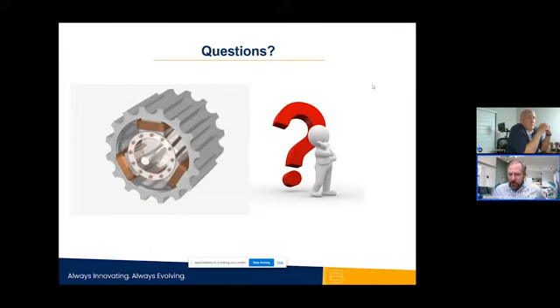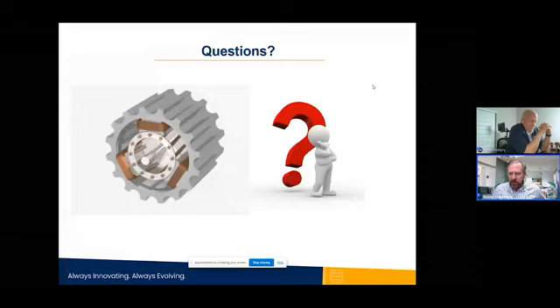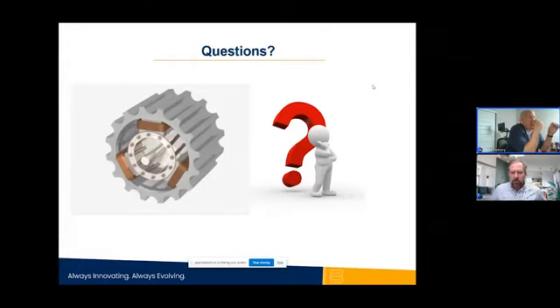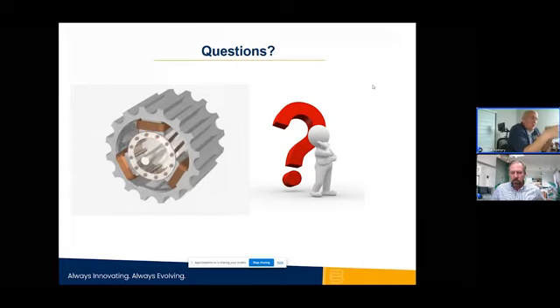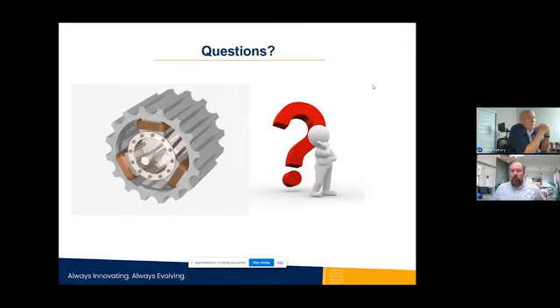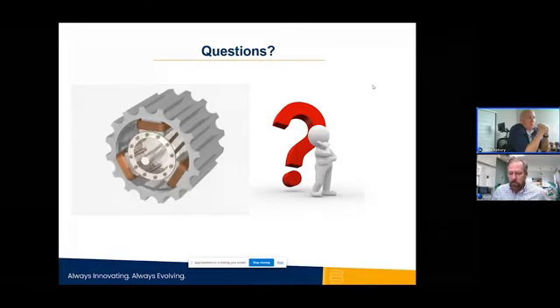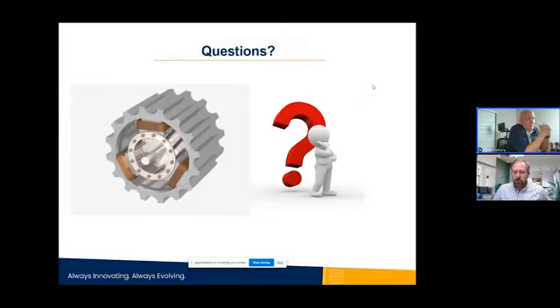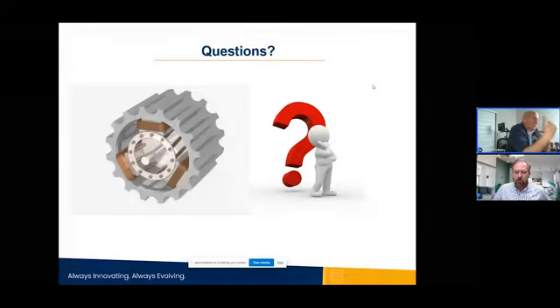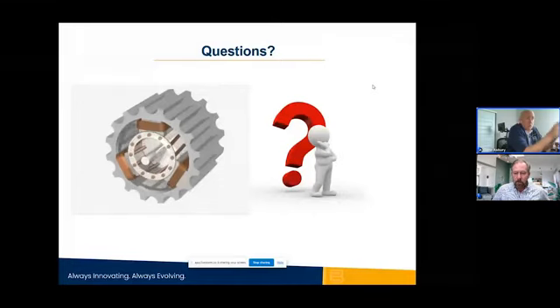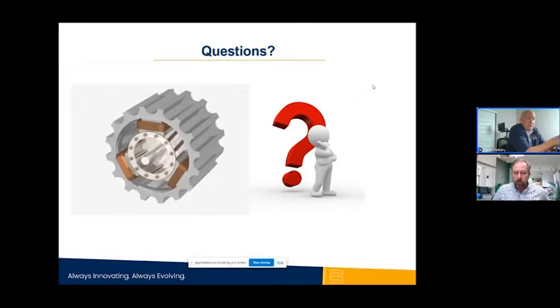All right, next question. What happens to the exciter panel DEX 250? Is it required to start the synchronous motor using a soft starter? It doesn't need to. It can, but what happens is the squirrel cage winding will actually start the process with the interaction between the RMF that's generated when the AC supply voltage is applied to the stator winding. So the interaction between the squirrel cage winding and the RMF will start the rotation. And then from there, it'll come up to synchronous or approach synchronous speed, and then something will tell us to apply the field either through a control unit that we discussed earlier, or maybe through a speed signal.